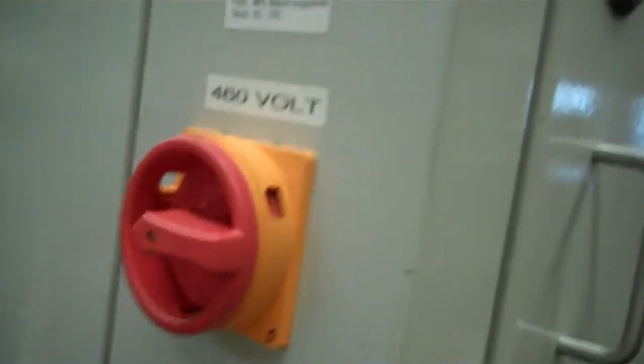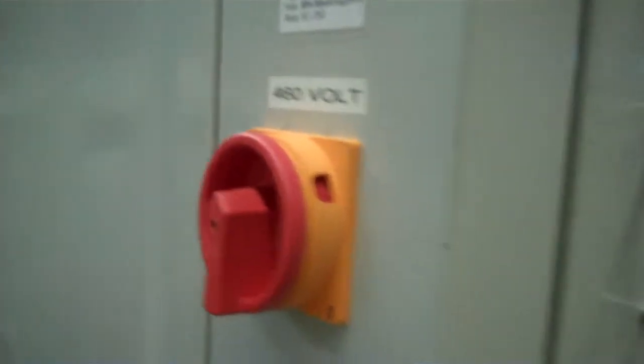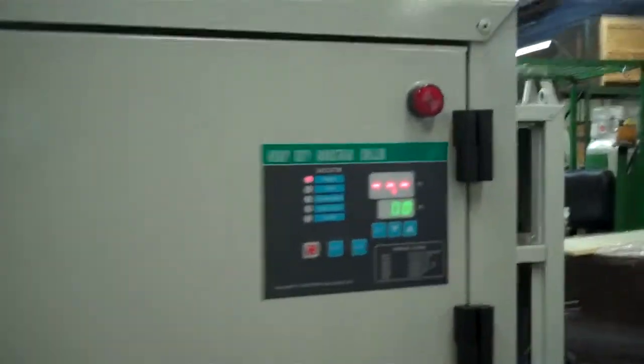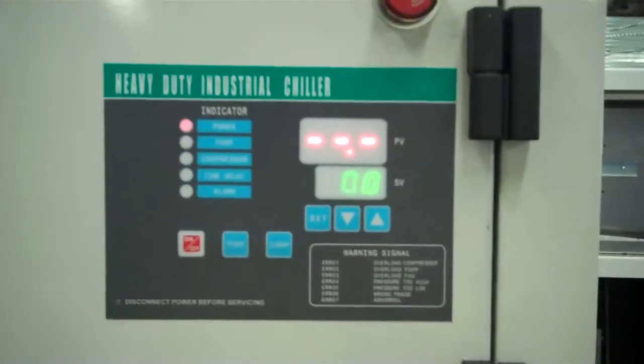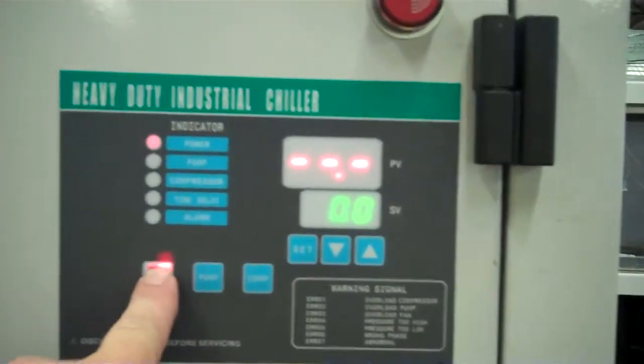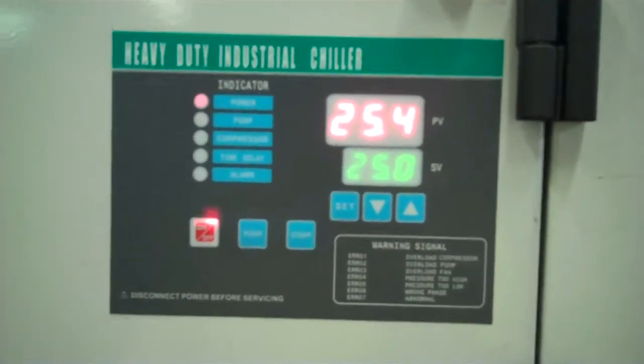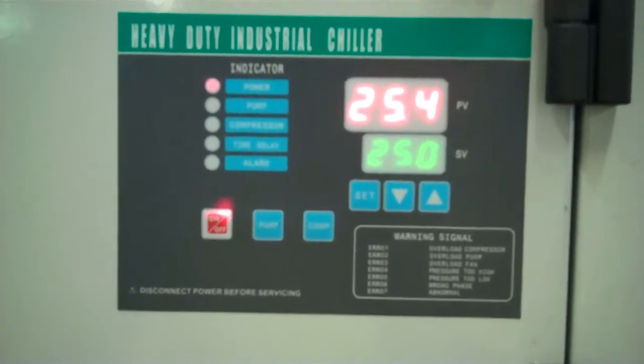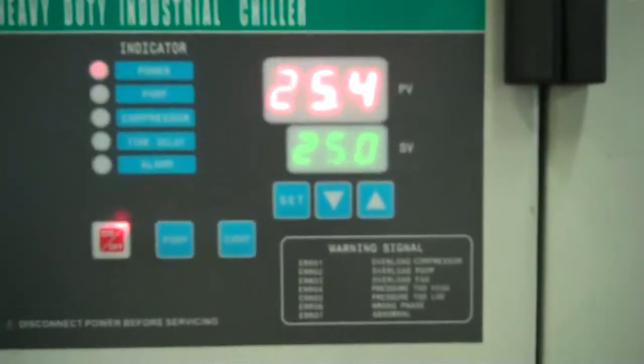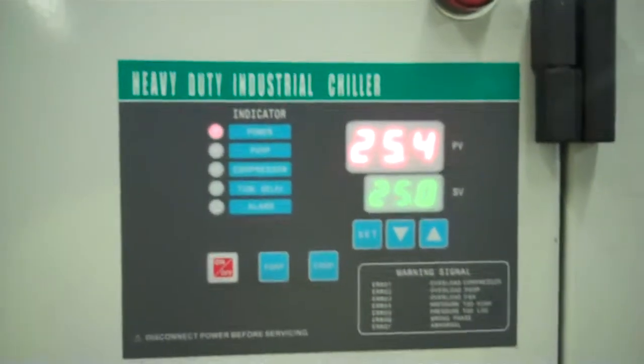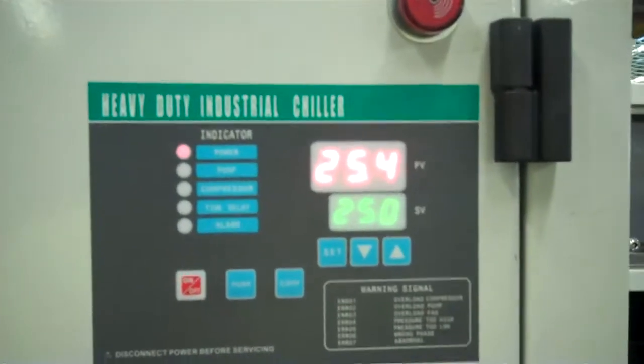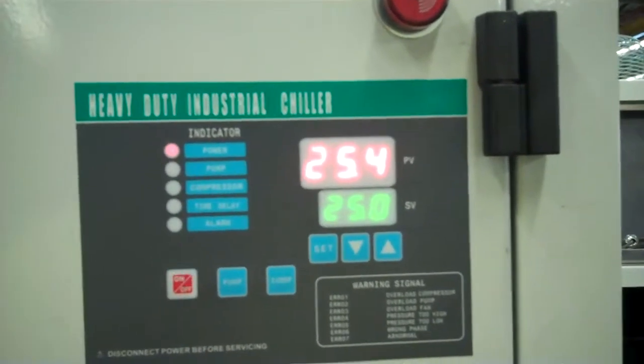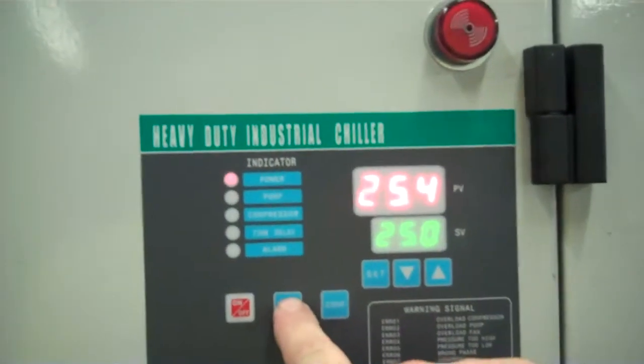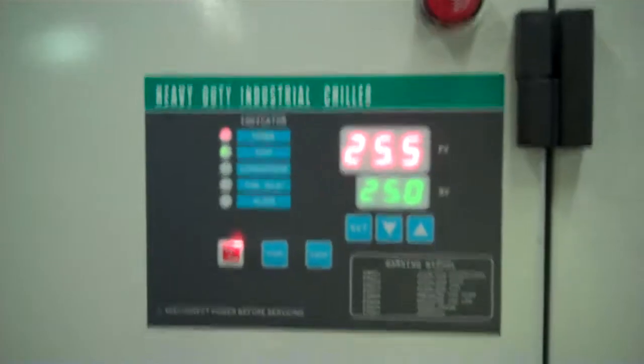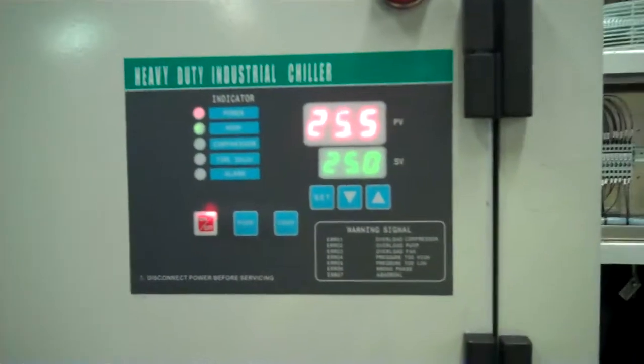We're going to start by just turning our primary power on here, and the control panel lights up. What we do next is we get the power on button, and you see the blinking light there. That simply means it's on standby. The units have a temperature range of 5 degrees C to 25 degrees C. We have the water in the tank heated up a little bit over 25. That equates to about just under 80 degrees Fahrenheit. First thing we do is turn the pump on and start flowing water through the system.